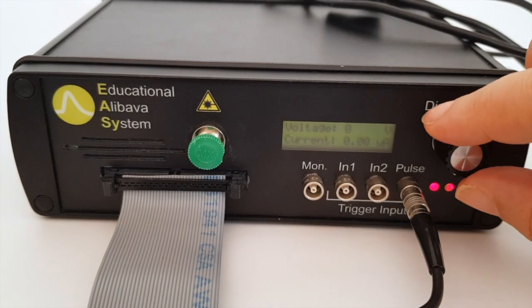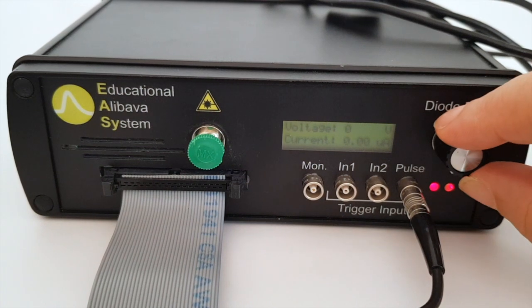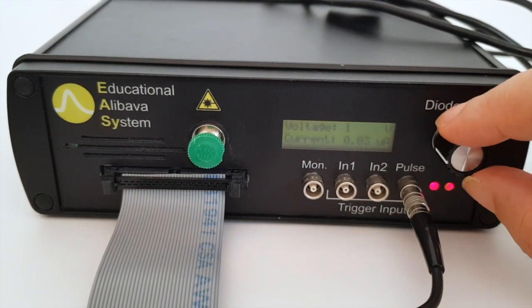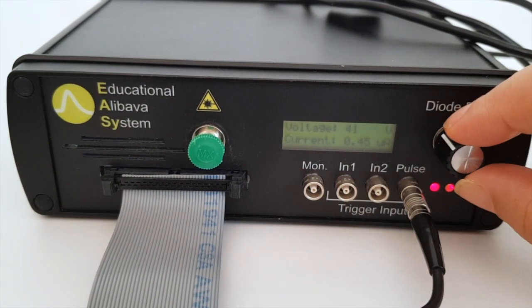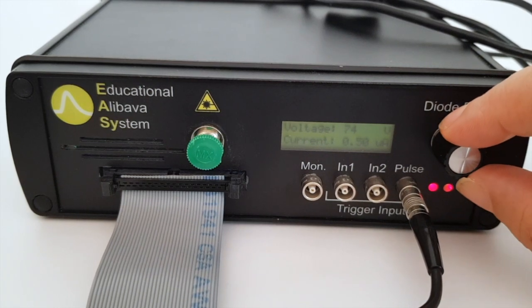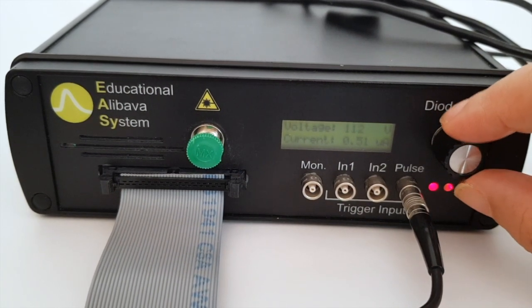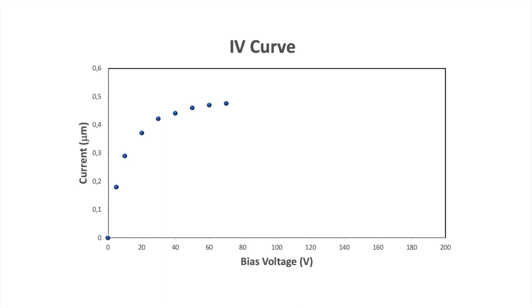After powering the control unit, we will measure the leakage current of the microstrip sensor for different applied bias voltages to plot the characteristic IV curve of a silicon sensor. A perfect detector shows a small rise in current at the beginning and then a long plateau up to the breakdown voltage. Some imperfections can cause the current to rise with voltage.